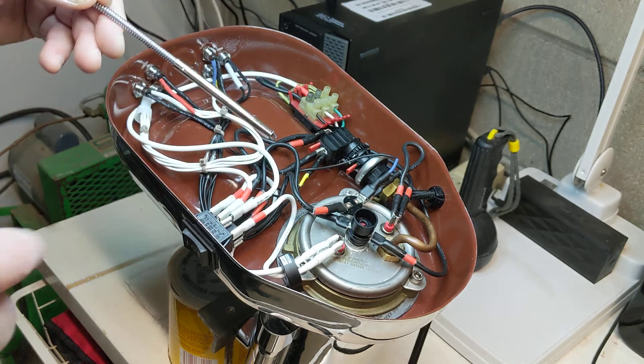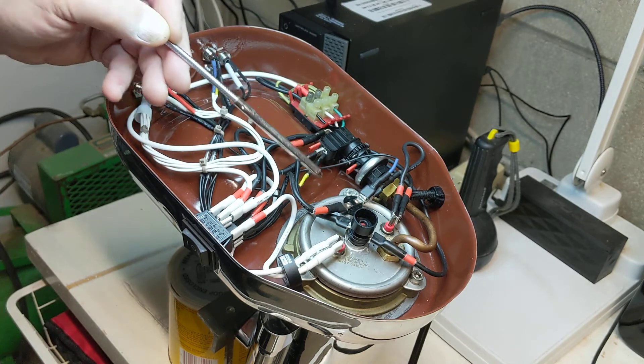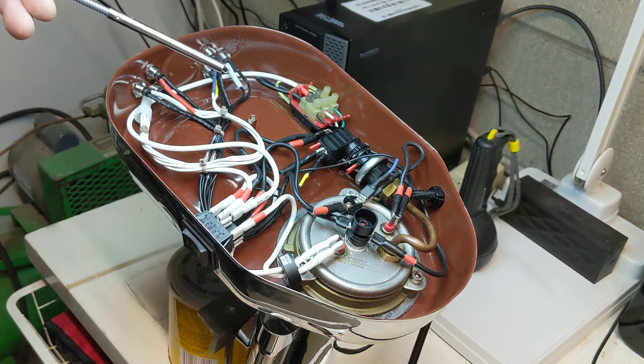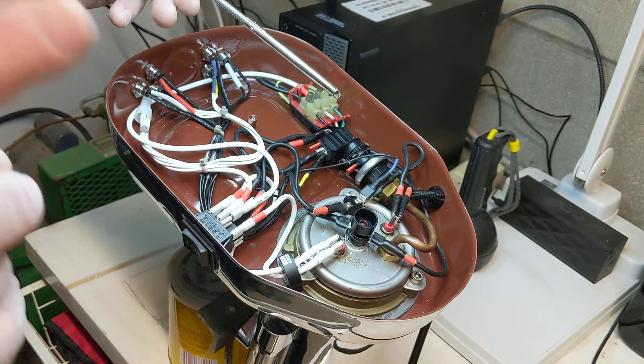The equipment ground is not necessarily maintained between the base and the boiler unless you have a separate ground. A lot of systems ground the base but forget to ground the boiler, or vice versa. Bong actually ran some experiments on this and figured it out.